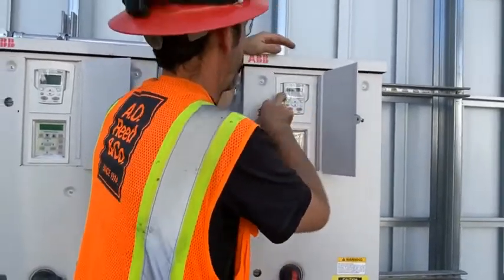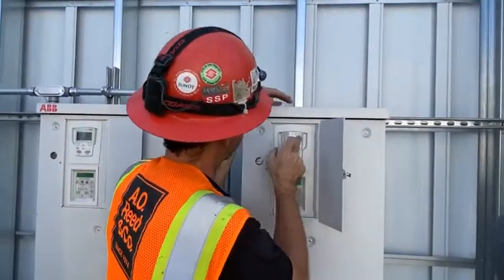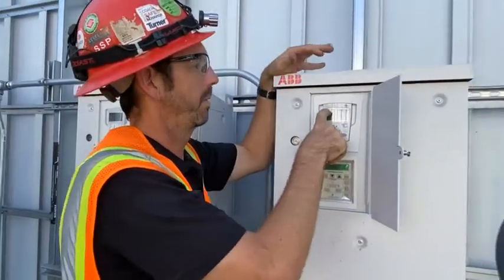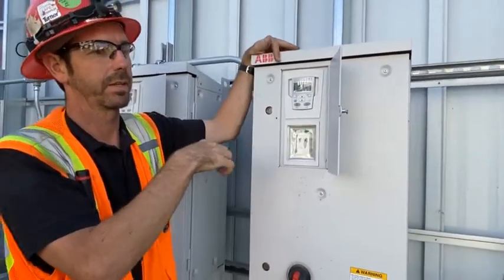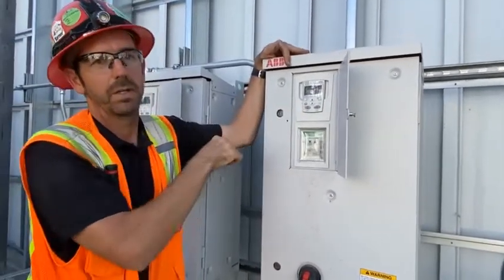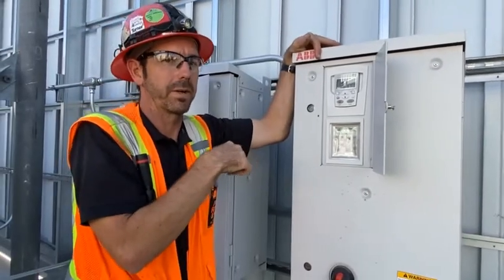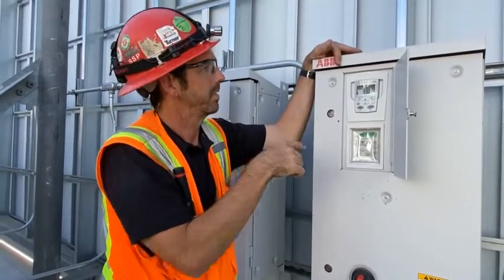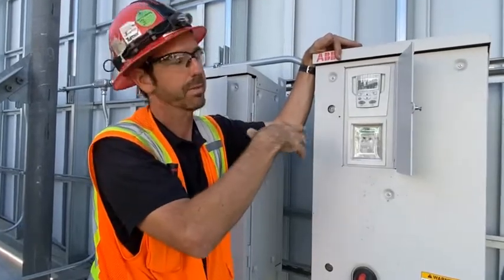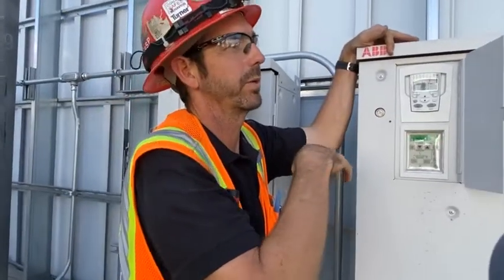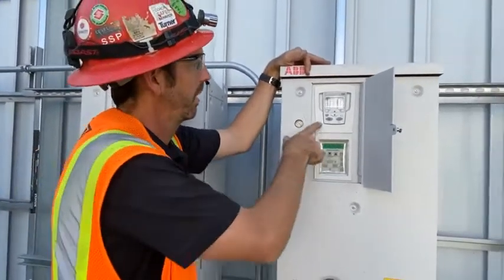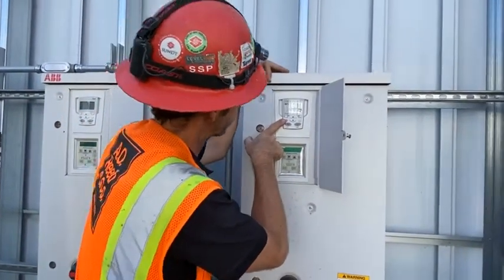Coming back over to this drive now that it's on and booted up. Again, the most important part with these VFDs is that the keypads remain in auto. Our control guys are finishing up some integrations to these two pumps right here. So currently these were off, okay? But we want to make sure when we're doing our day-to-day inspections of the equipment that each one of these is in auto mode, okay?